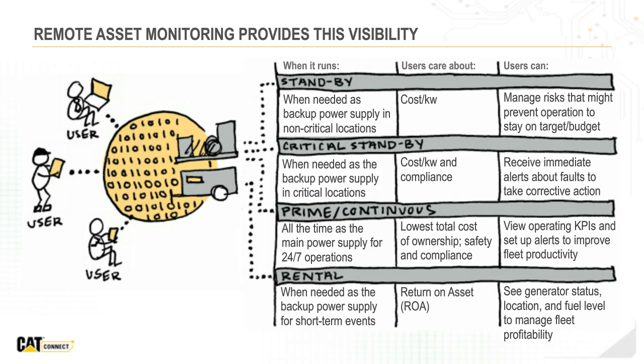The first one is the standby power application. This is one where people conceptually have a hard time understanding why you'd connect a standby genset when it's not really running. The reason we see such a tremendous increase in remote monitoring here is the assurance that the genset will start when you need it. It's added risk management for the genset.